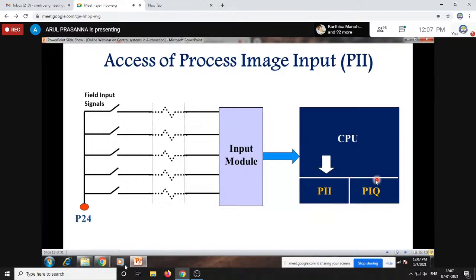One is PII, another is PIQ. In Siemens terminology, PII stands for process image input and PIQ stands for process image output. Siemens always mentions input with I and output with Q, whereas other competitors like Allen Bradley and ABB use input with I and output with O. These identifier terms vary depending on the manufacturer. In Siemens, I is for input and Q is for output, so while addressing, we give I for input and Q for output.